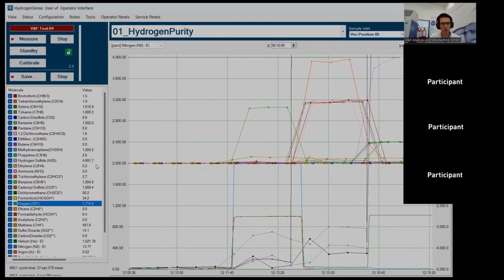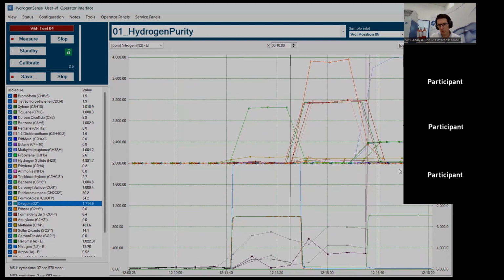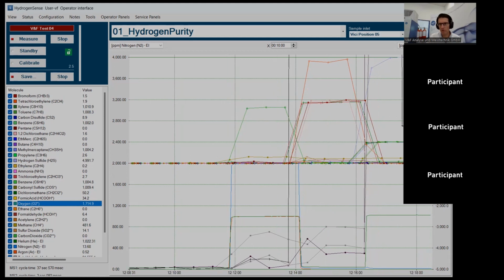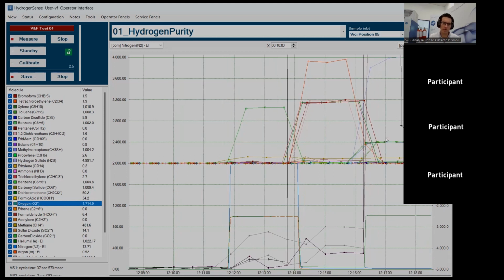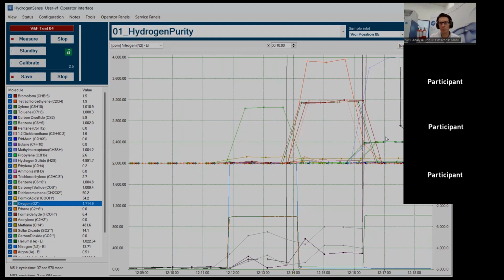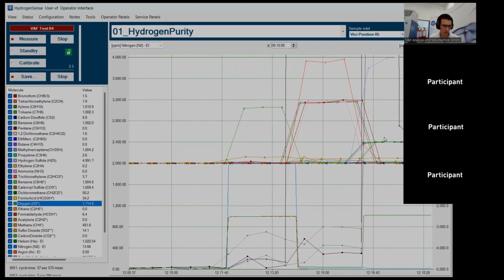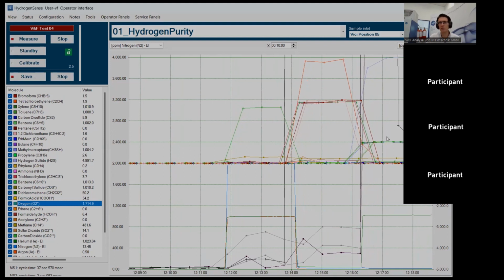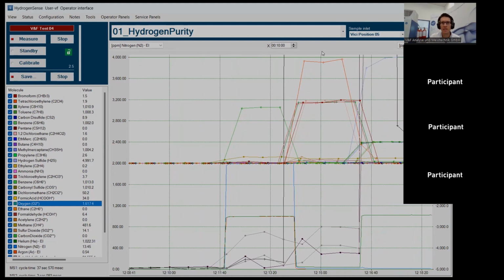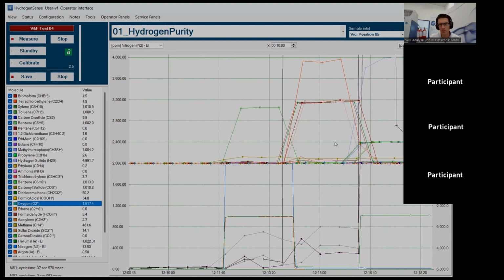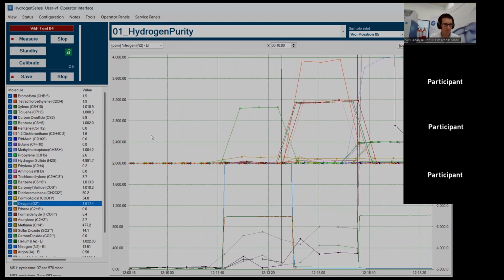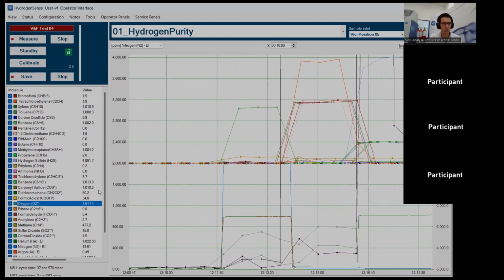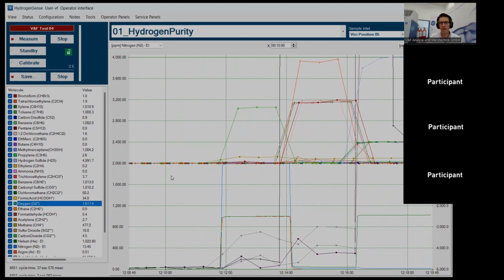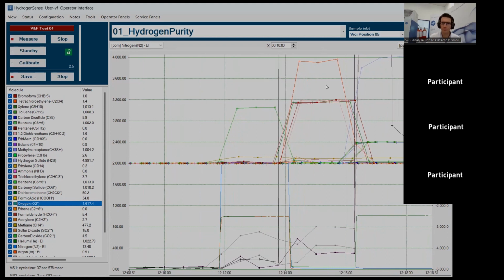So usually what we recommend is, right now here we are pretty much only looking for a few minutes, but we typically recommend to have a flush time of at least 5 minutes. So in order to get really the essence of the gas that you want to analyze into the spectrometer, then we run like 5 or 10 measurement cycles in order to produce the final value of the analysis.